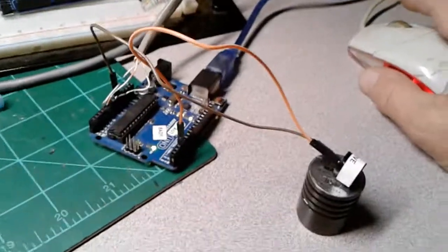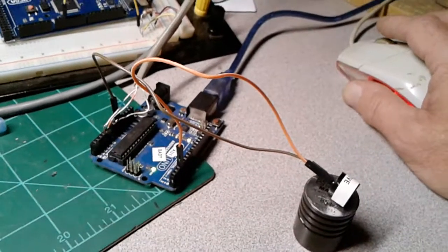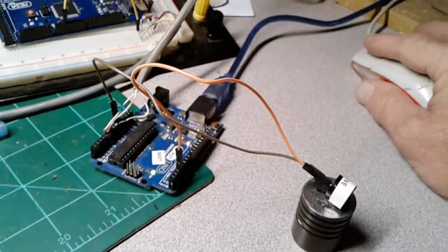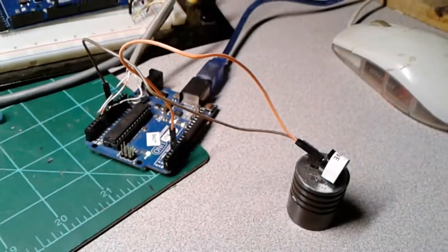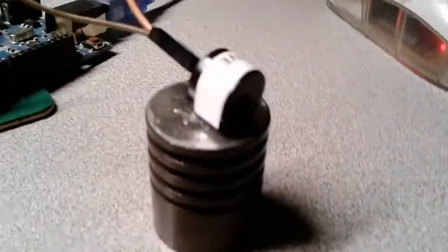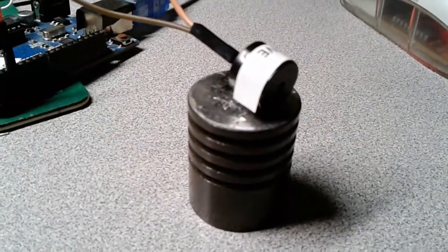Okay, here we go. I have disconnected the load from the antenna port, so it's a totally open transmission line, and we should have an audible alarm. So let's send the page. There it goes through the system, and there's the audible alarm. Should be for 5 seconds.